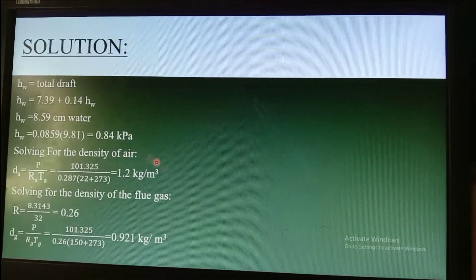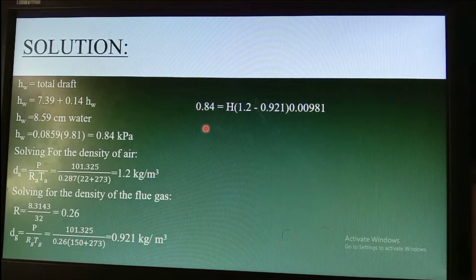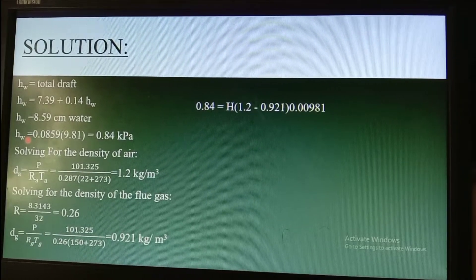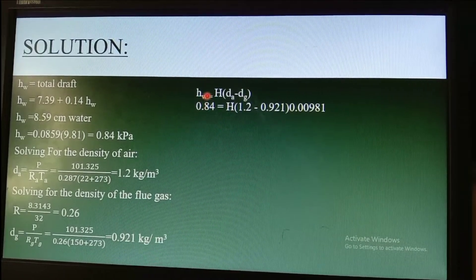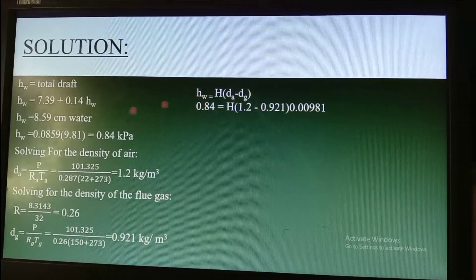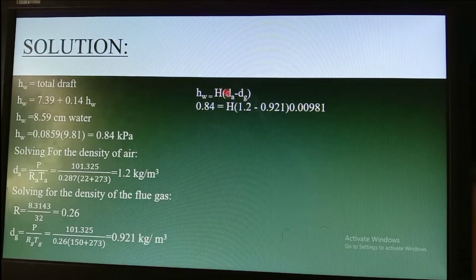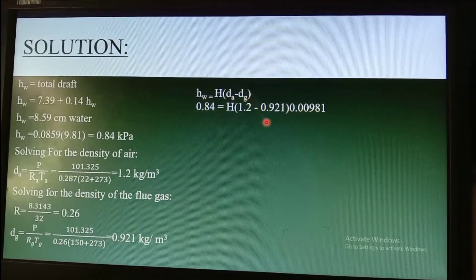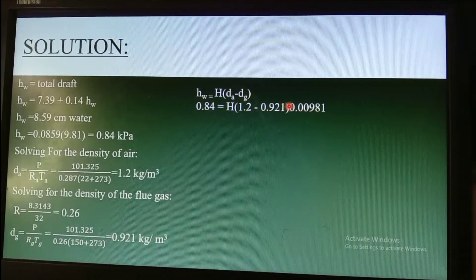Knowing the total draft and the densities of air and flue gas, we can now compute the height of the chimney. The total draft formula is: 0.84 = H × (Da − Dg), where H is the chimney height, Da = 1.2 kg/m³, and Dg = 0.921 kg/m³.